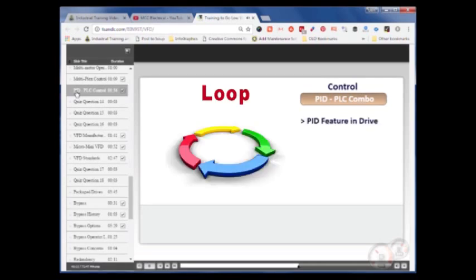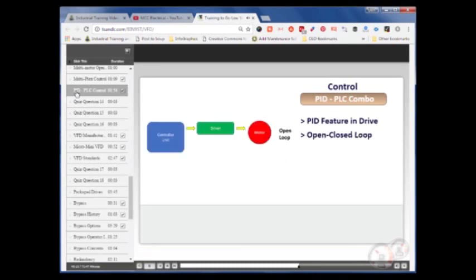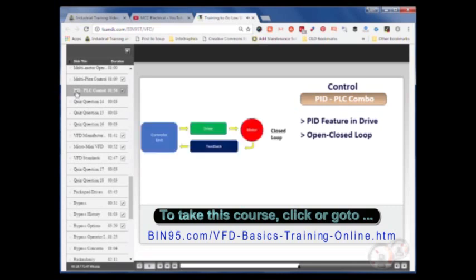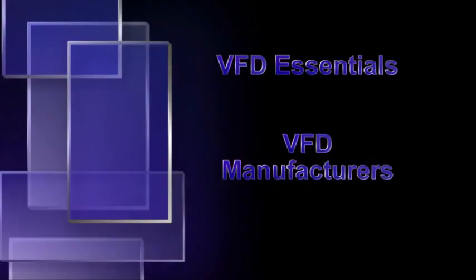Loop refers to the cycle of control. Open loop basically means that there is no feedback going directly to the drive. A closed loop system, however, provides more accurate control of the drive. In closed loop applications, PID settings and a speed reference are programmed. If the actual speed varies from the set point, it is referred to as an off the set point or offset for short.